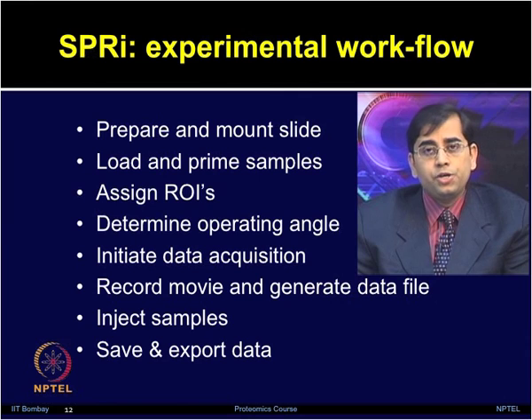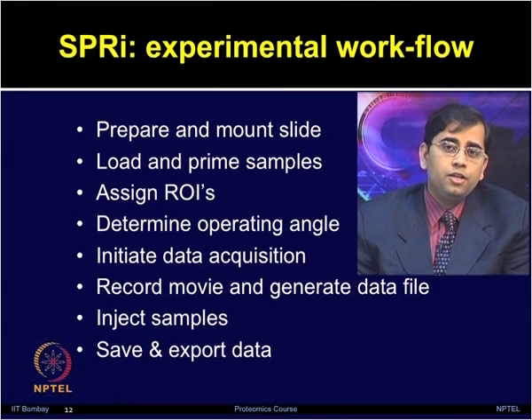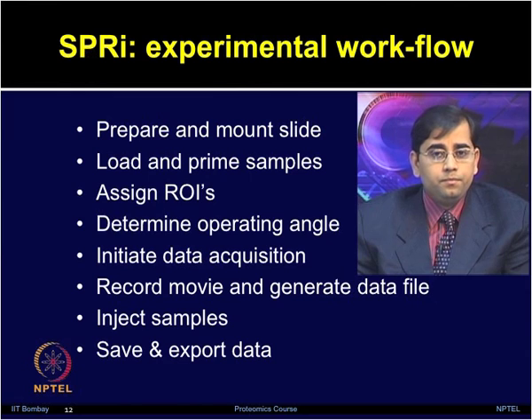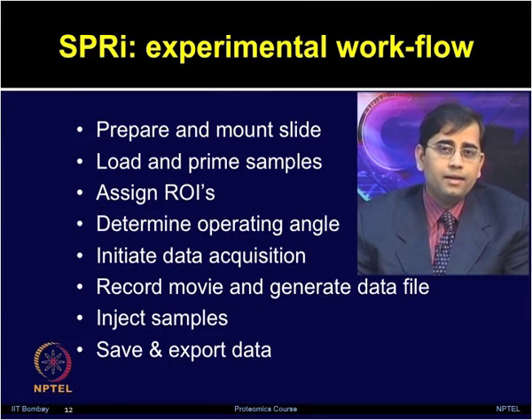Now let us talk about the experimental workflow involved in the SPR imaging experiment. The SPRI fixes on a single incidence angle and monitors the reflection intensity for the whole array as a function of time. Various steps involve preparation and mounting the slide on the prism, loading and priming the samples, assigning the region of interest, determining the operating angle, initiating data acquisition, recording and generating a data file, injecting the sample, and finally saving and exporting the data.